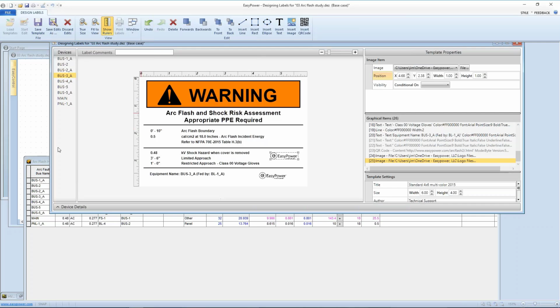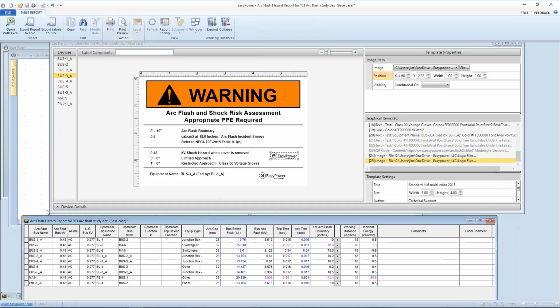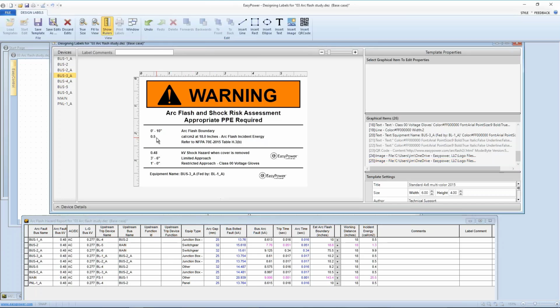For instance, on bus 3A, we're showing that bus 3A is a 480 volt bus. The arc flash boundary is 10 inches. The incident energy is 0.5 calories per square centimeter. Now, according to NFPA 70E, this information, 0.5 calories, is what the operator or electrician needs to refer to when he's selecting PPE to work on this bus hot. And he needs to comply with NFPA 70E table H3B. For shock boundary purposes, it's a 480 volt bus. 3 foot 6 inches is the limited approach, and 1 foot 0 inches is restricted approach.